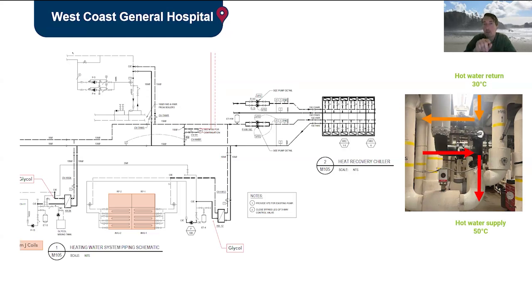And so what was happening was, and we learned this through our process with a series of different consultants, I'm on the owner side, but we had learned that there was bidirectional flow happening. And what was happening is the 50-degree water was short circuiting. And instead of being that 30-degree water returning back into the system, it was 45 degrees. So we really had a major impediment, and it made sense why post retrofit we really weren't receiving the benefits. And this also then in turn made the ability to utilize the chillers at their capacity constrained.